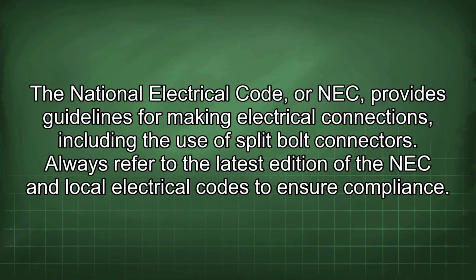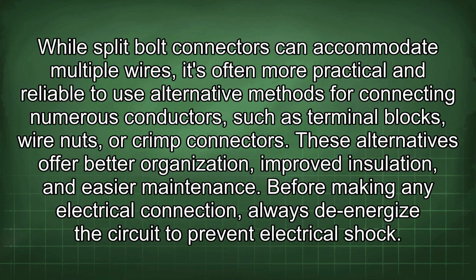The National Electrical Code, or NEC, provides guidelines for making electrical connections, including the use of split bolt connectors. Always refer to the latest edition of the NEC and local electrical codes to ensure compliance. While split bolt connectors can accommodate multiple wires, it's often more practical and reliable to use alternative methods for connecting numerous conductors, such as terminal blocks, wire nuts, or crimp connectors. These alternatives offer better organization, improved insulation, and easier maintenance.